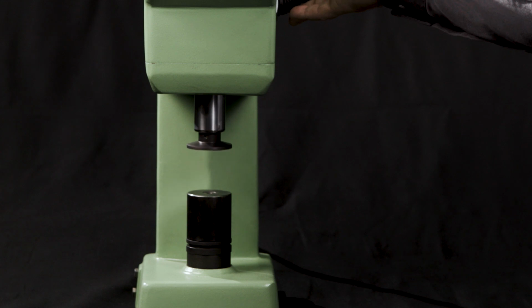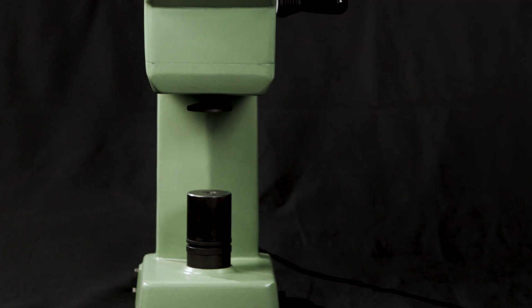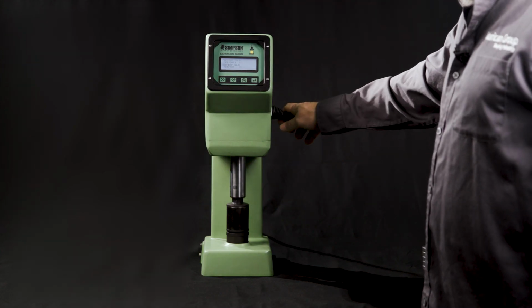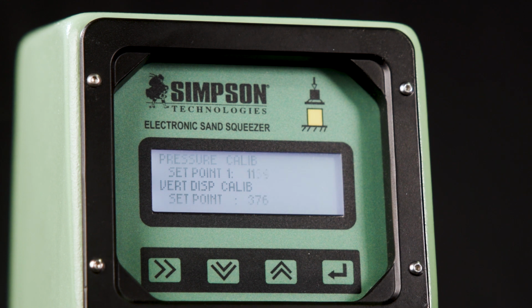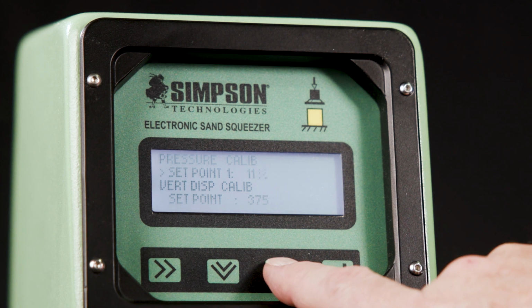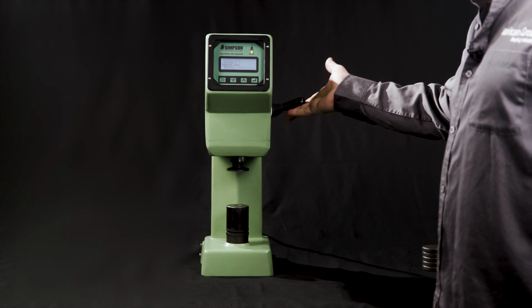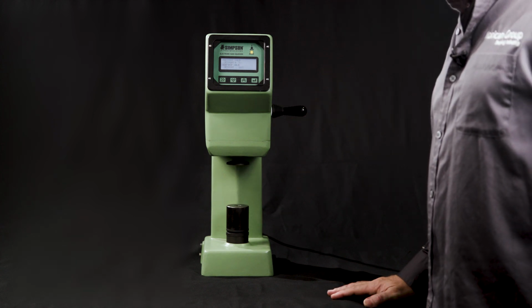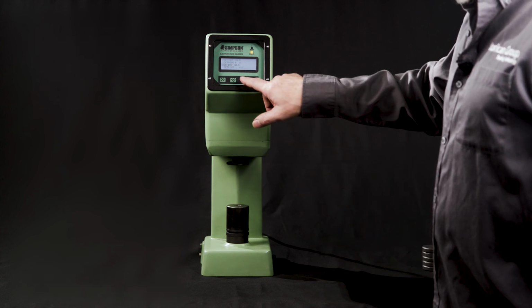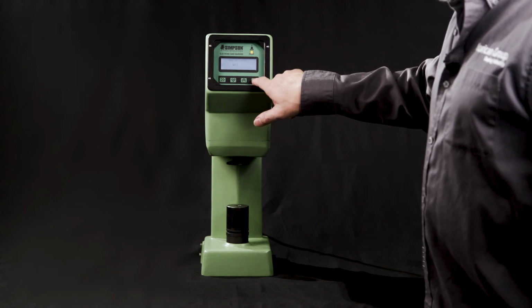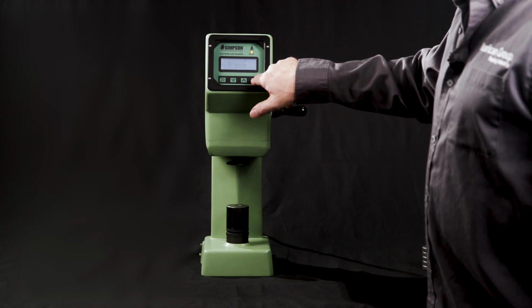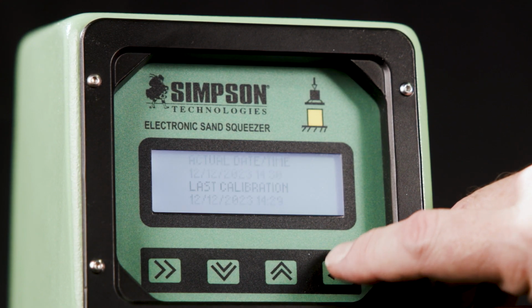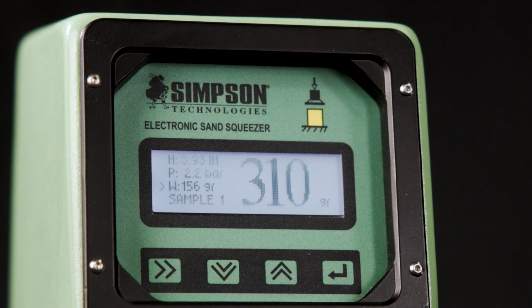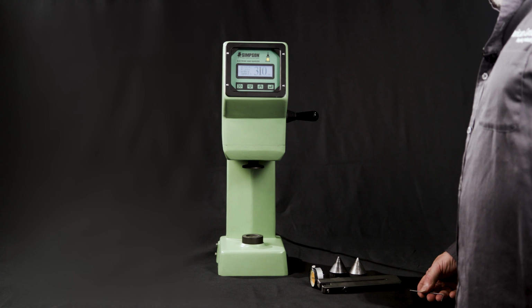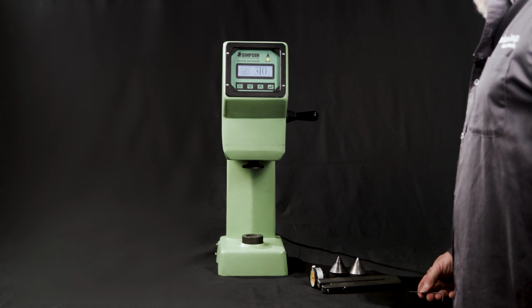We're going to bring this up to release some of the pressure, and then we're going to adjust the pneumatic regulator for 3 bar of pressure. At 3 bar of pressure, you'll see the piston is now moving faster. We're going to wait, stabilize, press that button, and now we've just set the range for the pressure calibration of the machine from 1 to 3 bar. And that is it for this calibration. At this point, we can press the return button, and that will go through the main menu functions of the machine until we get to where the main date and calibration is, and then it sets back to the main menu screen.